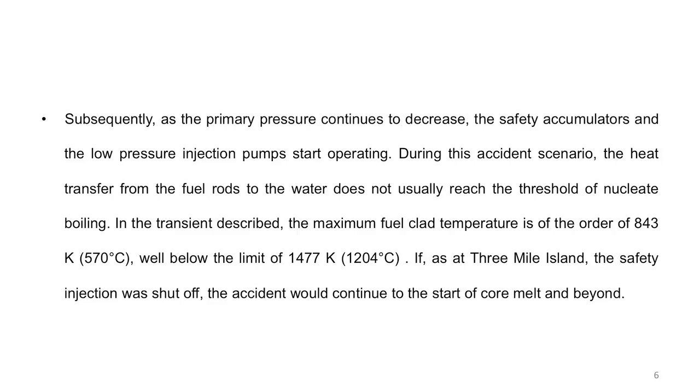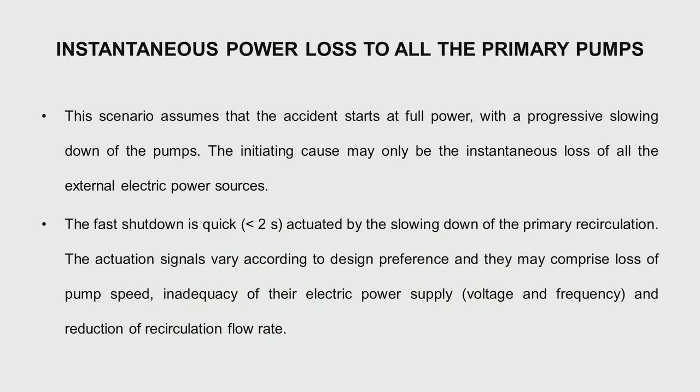You might wonder: if everything is okay and the temperature did not exceed limits, then why did Three Mile Island fail? The safety injection was shut off by the operator. Why? He found that the level in the pressurizer was rising, but he never realized it was rising because of steam in the core pushing water up, while the core itself was devoid of water. Unfortunately, due to lack of proper instrumentation, this happened. Otherwise the Three Mile Island incident would not have occurred. This is the event of a pressurizer valve stuck open.